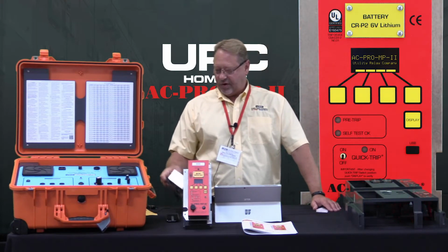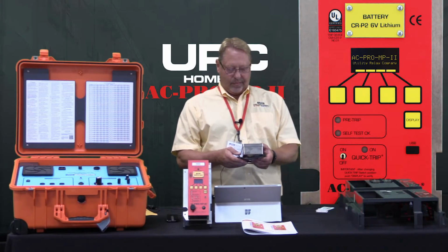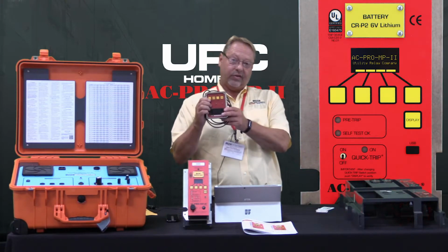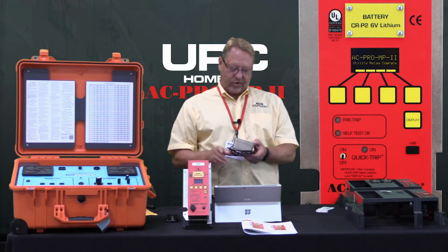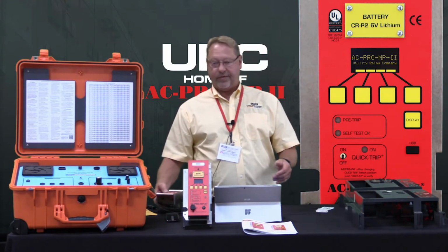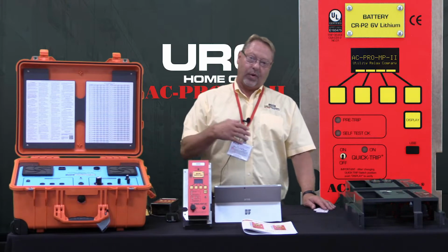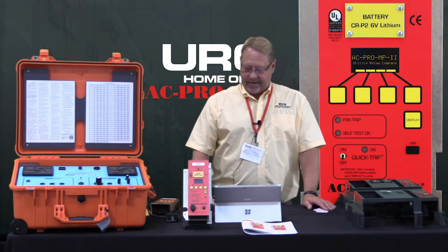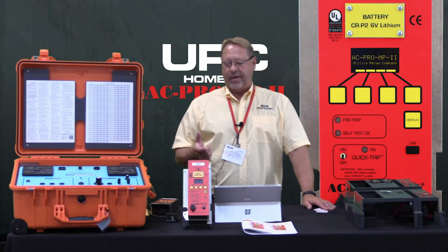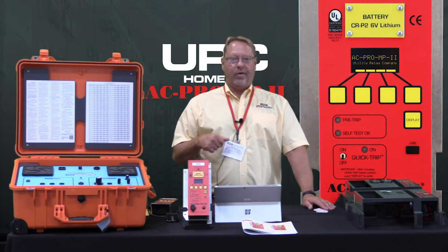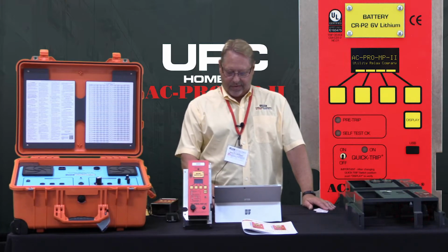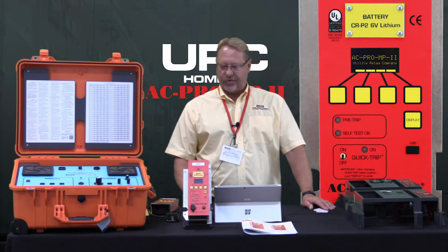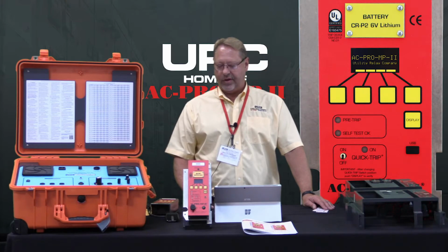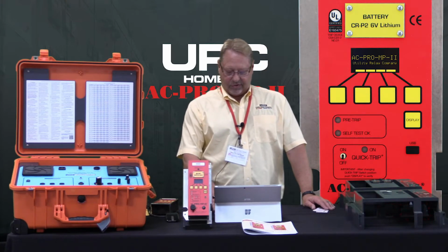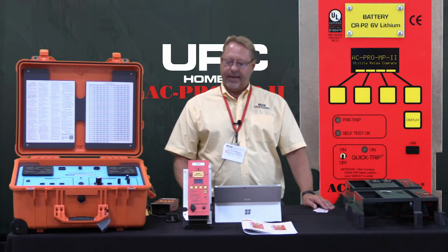Arc flash boundaries are important, so we added the ability to use a safety trip tool. It allows you to trip the breaker from 30 feet or 10 meters away, get you away from that arc flash zone. We date and timestamp when the breaker trips, so you know why it tripped. We give you current and voltage waveforms as well. We call it waveform captures. No rating plugs are required for the unit. So it's basically a direct replacement for the unit.